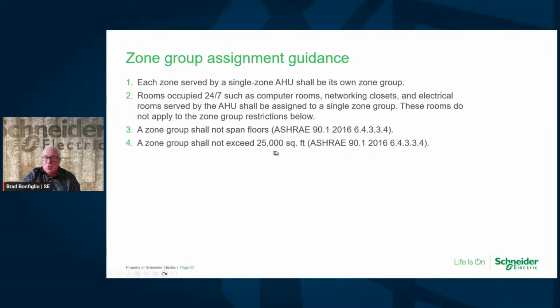You don't want to get too big in the zone group. So 25,000 square feet is the maximum for a zone group. You don't want one terminal unit feeding a vast space and another one feeding a vast space, and both of those add up past 25,000. So you obviously want the zone divided up, is the point of this. You don't want one being a bigger zone. So look at that across, and that's with ASHRAE. You can see the references to the ASHRAE standards we have.